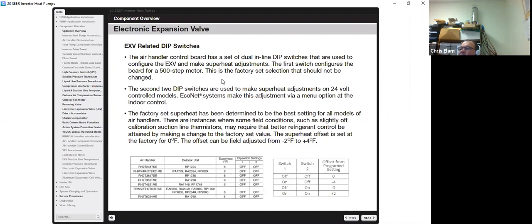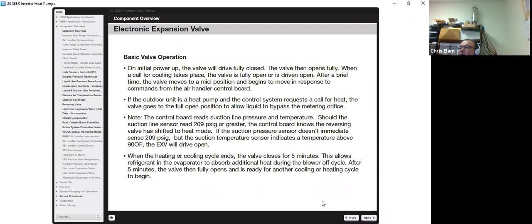The second two dip switches are designed to make superheat adjustments on a 24-volt control model. EcoNet systems make the adjustment via the indoor control. The factory set superheat has been determined to be the best setting for all models of the air handlers, as well as the RCF coils. There are some instances where it can be slightly off calibration, where you may try to dial in a specific value. So the superheat can be adjusted to negative 2 degrees superheat, so about 4 degrees, or you can go up to plus 4, which will give you 10 degrees.